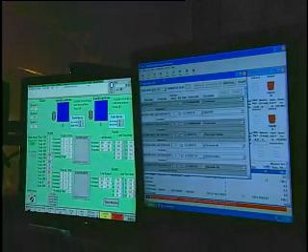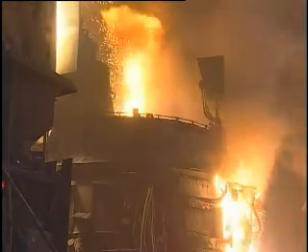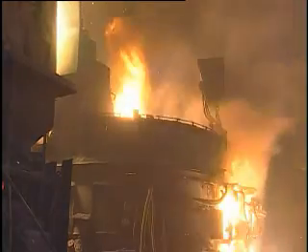The biggest benefit that we received was our improvement in the holes in the furnace. We use RTDs to sense heat on the side of the furnace that can come either from an arc deflection, from an arc flare, or from blowback on our cojets. We were able to historize this much more accurately, and we were able to come up with more sophisticated controls. This allowed us to do two things, actually.